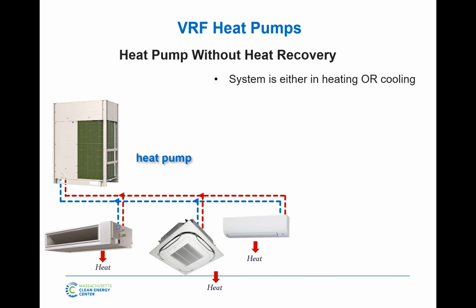There's two pipes for all manufacturers. There's two pipes that go out to the system. One's a supply, one's a return. Again, it's liquid and suction, or it's hot gas and liquid, depending on the mode. What that means is if I'm in heating mode, that's my discharge pipe. I'm sending you hot gas, and if you want heating, you can get heating. You can decide that each expansion valve can say, I want more or less heating. But you can't get cooling right now because I'm just giving you hot gas. And the blue line becomes the return, the liquid return line.